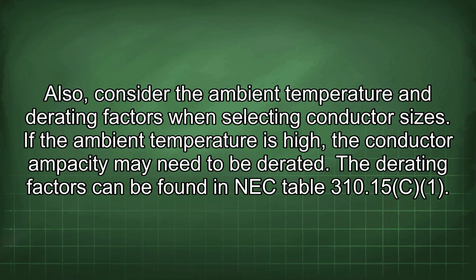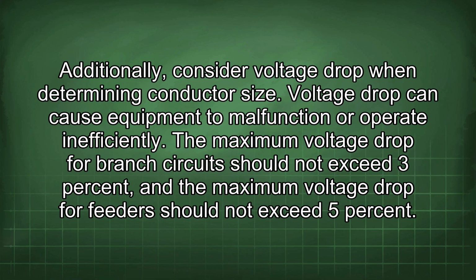Also, consider the ambient temperature and derating factors when selecting conductor sizes. If the ambient temperature is high, the conductor ampacity may need to be derated. The derating factors can be found in NEC Table 310.15. Additionally, consider voltage drop when determining conductor size. Voltage drop can cause equipment to malfunction or operate inefficiently.